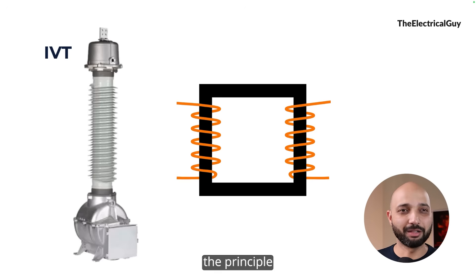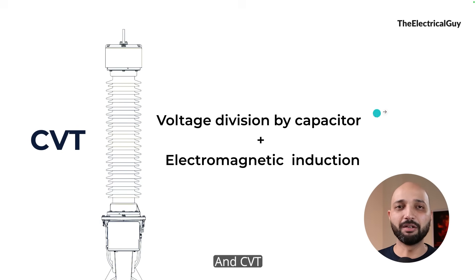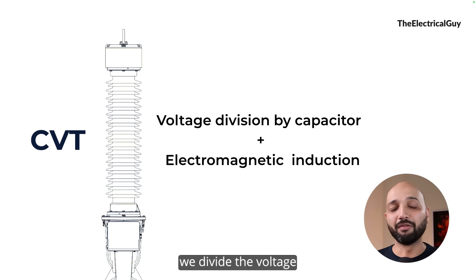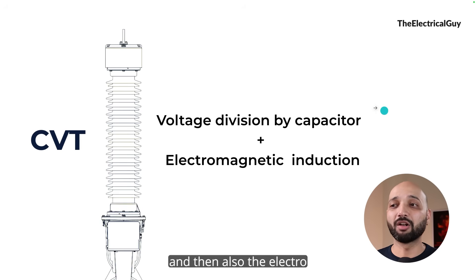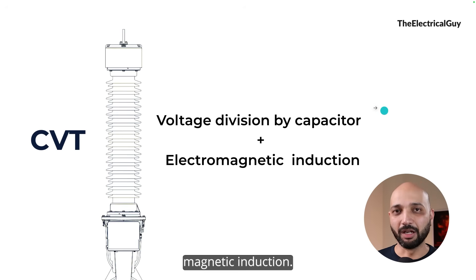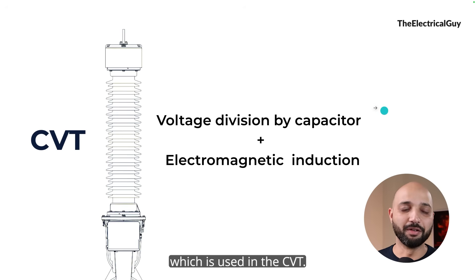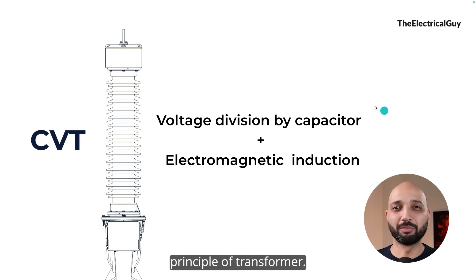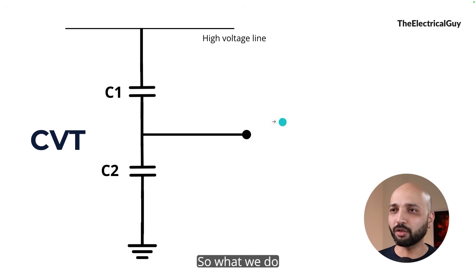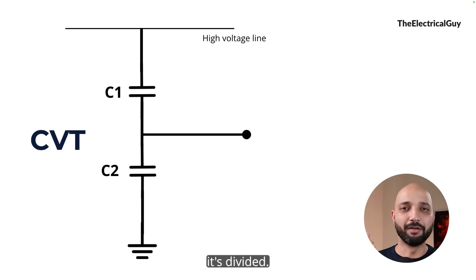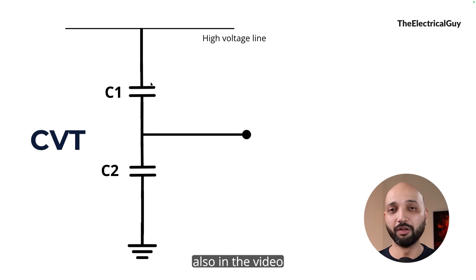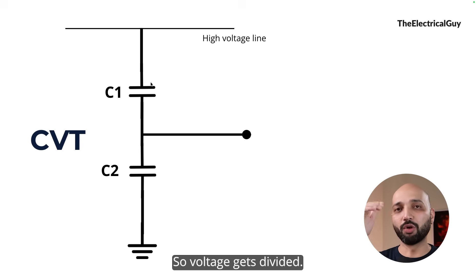When we talk about the capacitive voltage transformer, the principle is a little different. In a CVT, two principles are used: first, voltage division by capacitor, and second, electromagnetic induction. IVT uses the regular transformer working principle, whereas CVT is different. When you connect capacitors in series with the source, the voltage gets divided — as we saw in the simulation video.